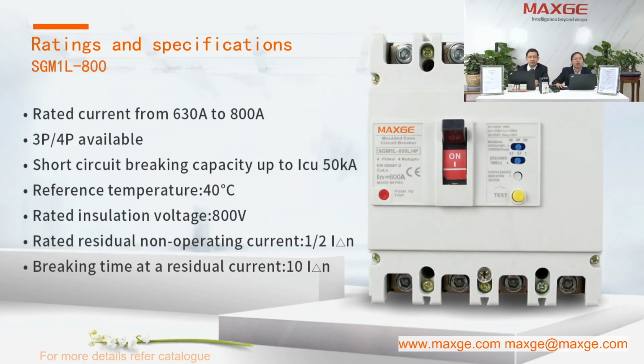The last frame is the 800 frame, the rated current from 630 to 800 ampere, and we have 3-pole and 4-pole available. And also here, from the specifications, you can see we can adjust the rated residual non-operating current and also the breaking time at residual current. So both the leakage current and the leakage time can be adjusted.